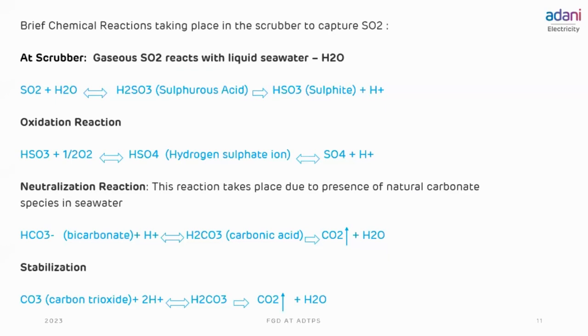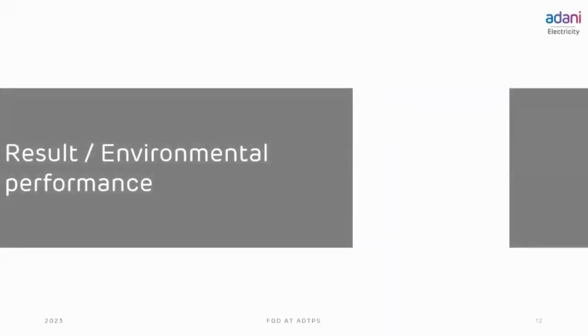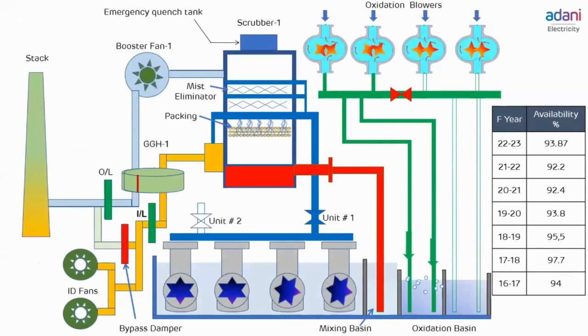The seawater for the scrubber is drawn from the condenser cooling water, which is used for the power station. The condenser cooling outlet has capacity to supply enough for the sulfur dioxide absorption and mixing. The scrubber exit water from the bottom of the scrubber flows through GRP-GRE duct and line by gravity to the mixing basin. The main purpose of this mixing basin is to mix this scrubber water from both scrubbers and remaining condenser seawater to bring the pH of the mixed water to a minimum of 6.5, because this water is acidic, so we have to raise the pH of this water.